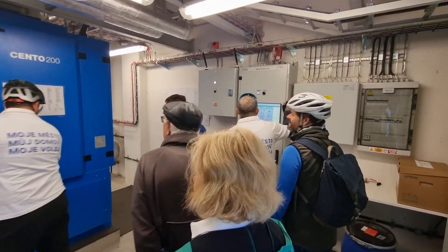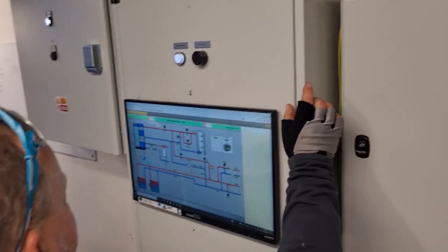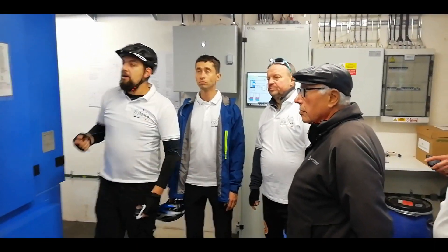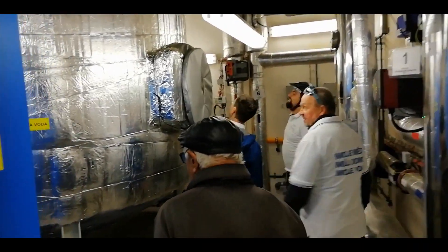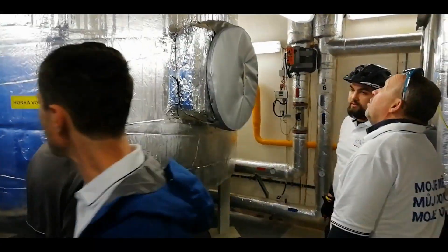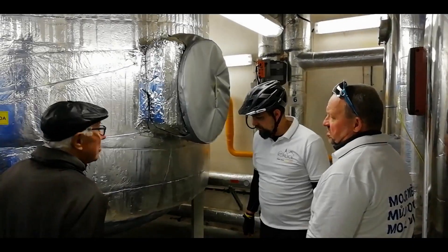This is an electric cogeneration unit — 200 kW electric output; at another location we have 800 kW. This is already the fourth cogeneration unit in Česká Třebová in Teza's boiler houses. Another cogeneration unit is being prepared for installation at the covered swimming pool. The cogeneration units are owned and operated by ČES Energo. Teza then rents the space and purchases heat from them at a favorable price. The use of cogeneration units is thus advantageous for reducing the overall cost of heat.